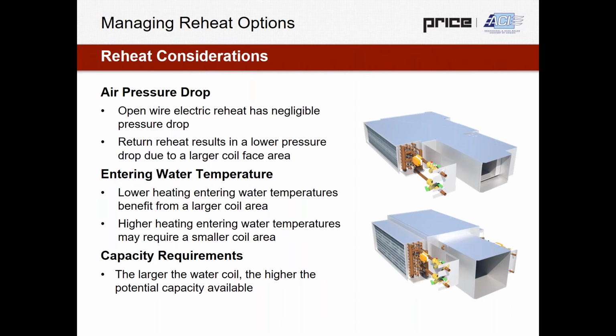So for instance, the first would be air pressure drop. When we look at air pressure drop and energy efficiency, the less resistance to airflow we can provide in the ductwork with our equipment, the more efficient our system is going to be overall. An open wire electric reheat coil has very negligible pressure drop, so that's maybe the optimal selection in terms of pressure drop. However, there's other benefits as well. If we look at a return reheat coil with a much larger coil face area, that's going to result in a much lower air pressure drop than, for instance, a discharge coil downstream of the equipment.